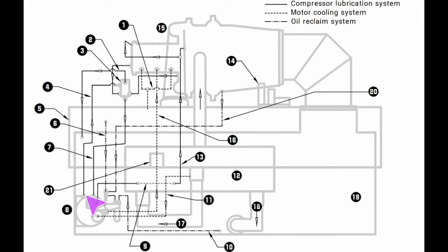The other part of this refrigeration cycle, and this is kind of the final piece for what we're dealing with, the rest of this will pertain to the oil management side, is we feed up. This is your vent right here that goes back to the evaporator. So any vapors, anything that collects in the top of this tank or the sump is allowed to process through this pipe here into this little oil separator we were discussing earlier.